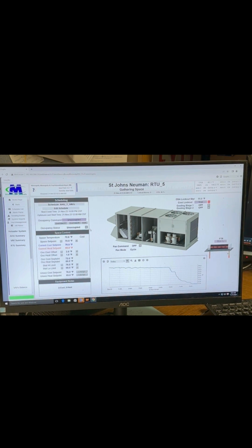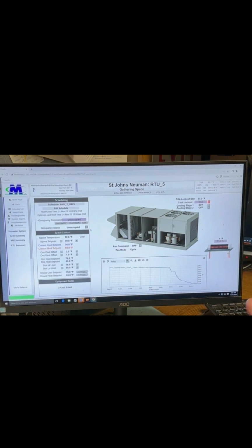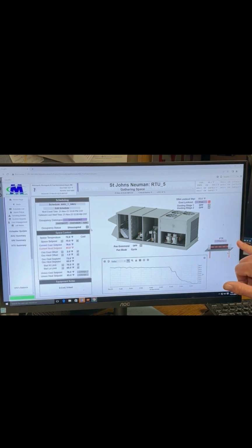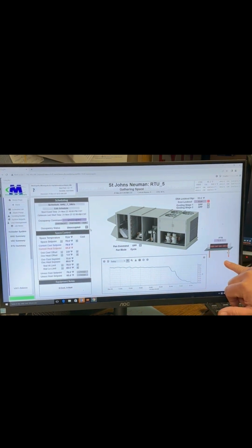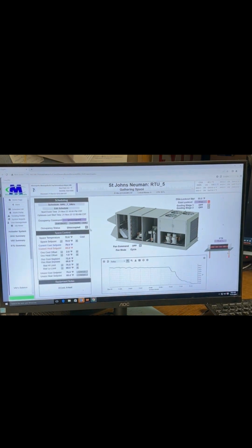Oh, the heat valve. Yep. Got it, okay. And if it gets above 70, if you're unoccupied, but you don't want it unoccupied, you want it running. Yeah. But if I separate this fin tube, it won't care about anything other than its set point and this temperature. Okay. And that's what you guys want. Yep. Because during the summer, we shut down the boiler completely. Got it. So the fin tube won't ever run. Got it. Okay. I can do that for you.